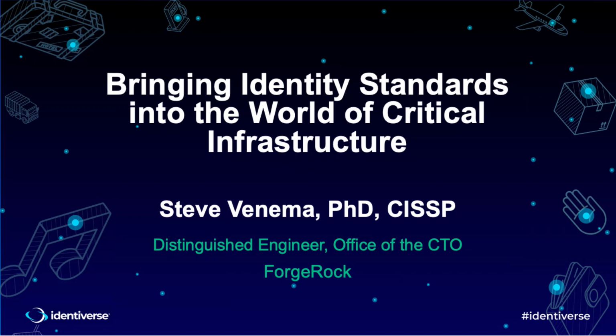I learned that firsthand at Boeing. I loaded a service pack. The human machine interfaces run something like Windows NT or whatever, right? I was helping set up a new moving line controller for the 777 line in Everett. And I thought, oh, well, gee, service pack 3's out, let's load it. I did that. I turned it into a brick. I had to have the integrator come out, flatten the entire system, and reload it. Fortunately, we weren't in production yet, but lesson learned. So really, any use of identity standards, we have to adapt to the requirements of the OT domain.